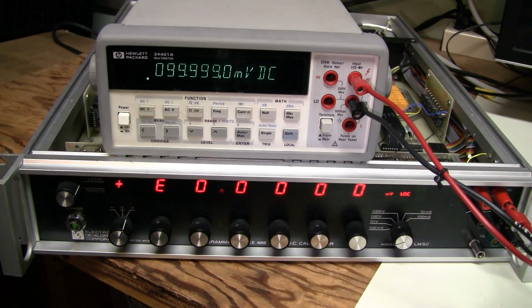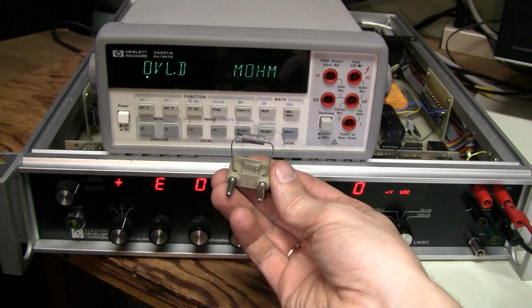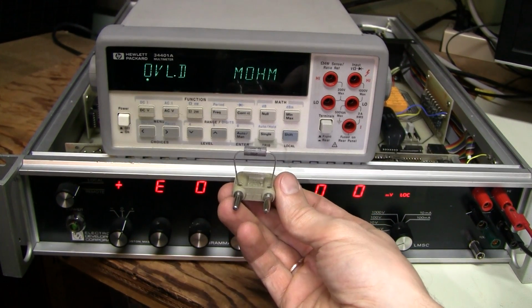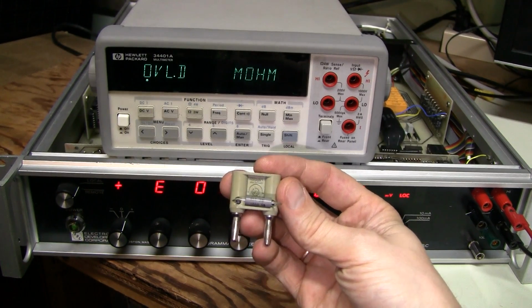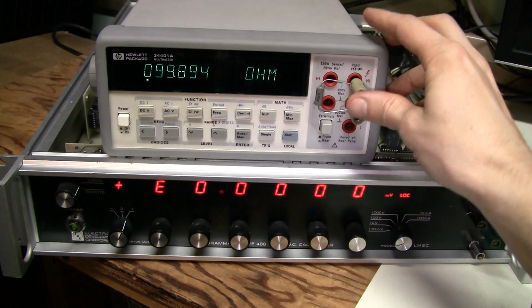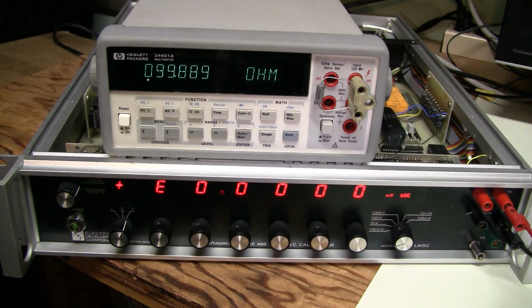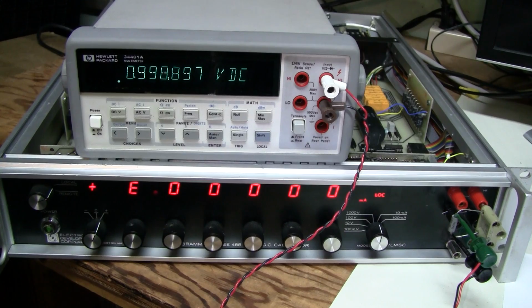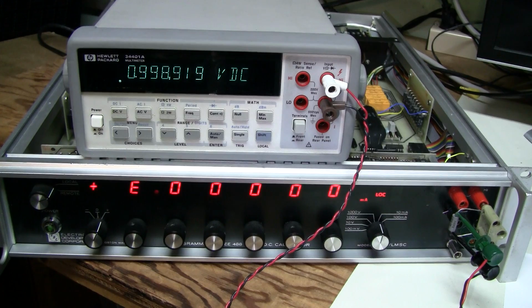For this we need a precision 100 ohm resistor. Let's see what I got. And this is the best 100 ohm resistor I have at the moment. 5%, 3 watts, and it happens to be within 0.1%. Should be good enough. So now in the 10 milliamp range we need to adjust this reading to 1 volt plus minus 20 microvolts. Alright, I adjusted, but not to 1 volt, but to the value of resistor 99892. And now we need to do the same in 100 milliamp range.